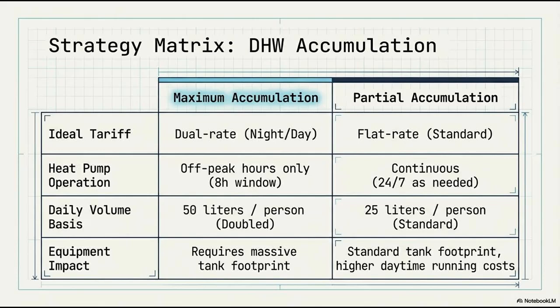Which really adds up. So to see if that grocery store strategy actually holds up mathematically, I dug into this case study provided in the document. The Rivne scenario. Yes, the Rivne reality check, I call it. So it's a 120 square meter new build in the city of Rivne, housing a family of 3. And what struck me immediately is the temperature differential the system has to fight. Oh, it's brutal. Yeah. Winter temperatures in Rivne drop to negative 21 degrees Celsius. And the groundwater entering the house is sitting at a chilly 10 degrees. But the family wants that water heated up to 50 degrees.